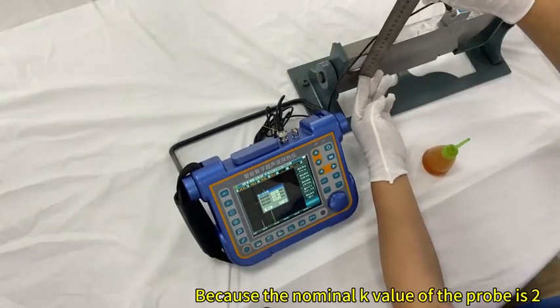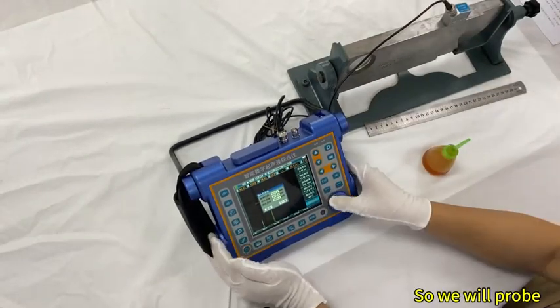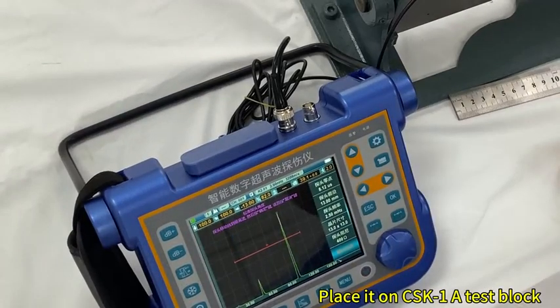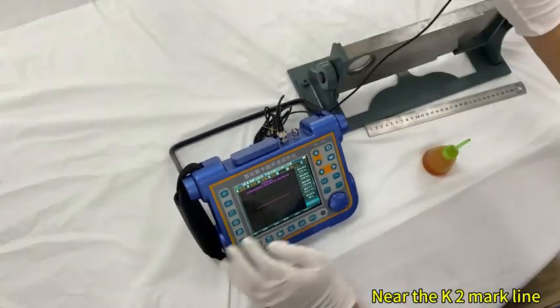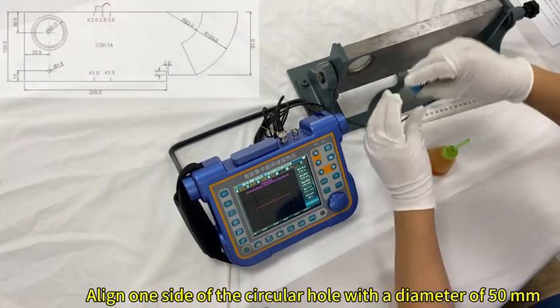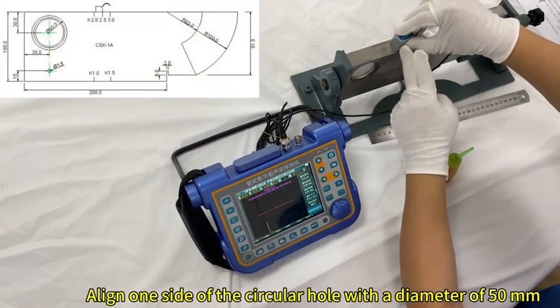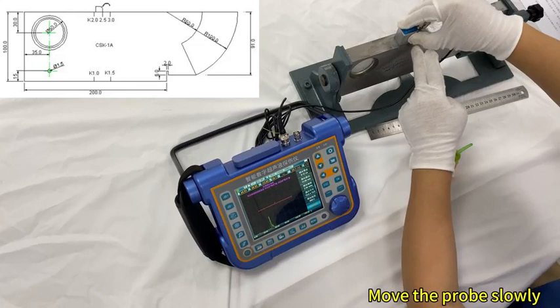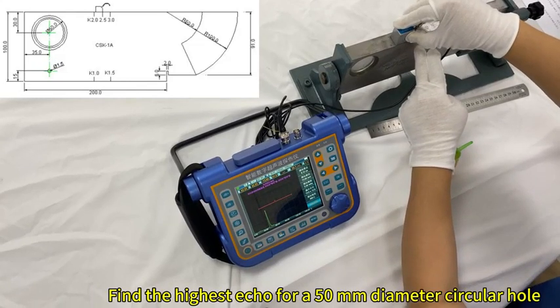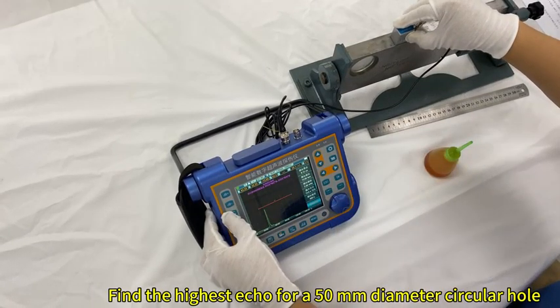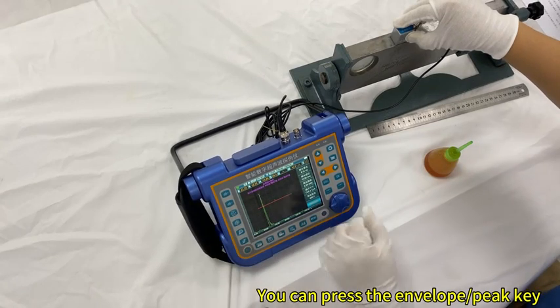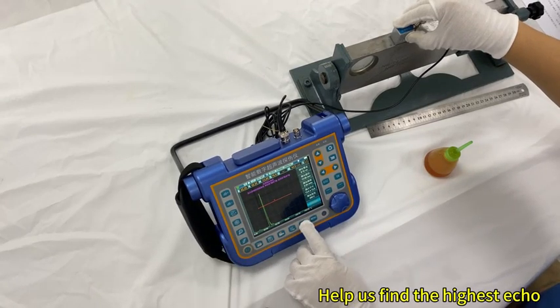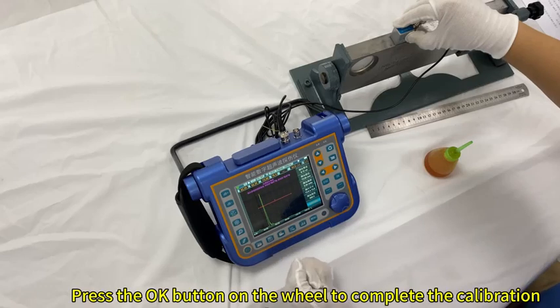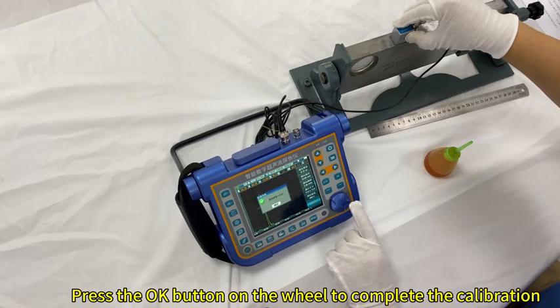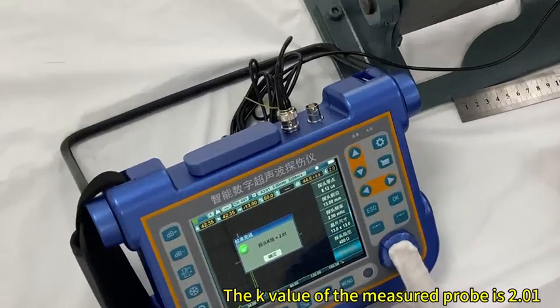Because the nominal K value of the probe is 2, place the probe on the CSK1 test block, near the K2 mark line. Align one side of the circular hole with a diameter of 50 mm. Move the probe slowly. Find the highest echo for the 50 mm diameter circular hole. You can press the envelope peak key to turn on peak memory assist, which helps us find the highest echo. Press the OK button on the wheel to complete the calibration. The K value of the measured probe is 2.01.